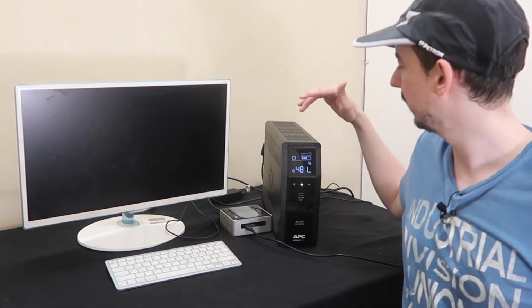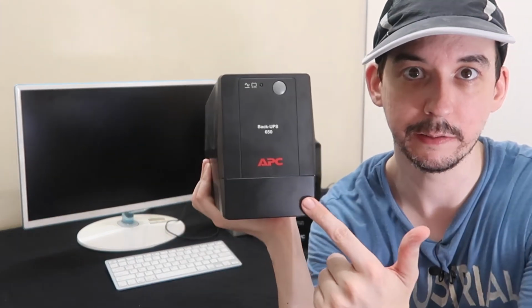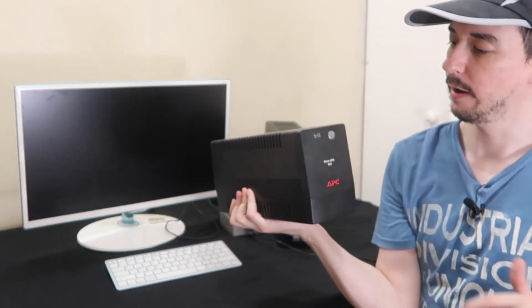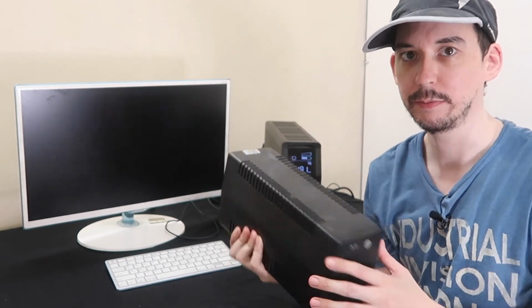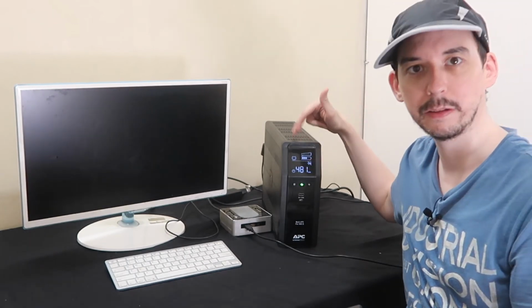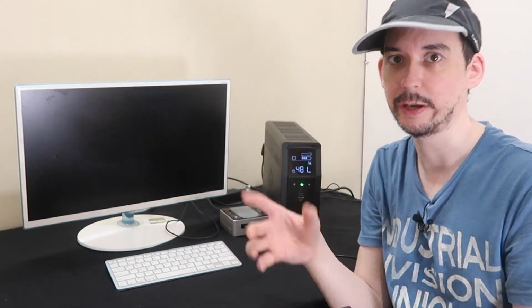So another difference between this UPS and this one here, this is also APC. I bought this myself. This is modified sine wave, and this bigger one is pure sine wave. So anything that's plugged into this is nearly the same as plugging it directly into your wall. Whereas what you plug into this gets a modified power. So instead of being a nice, smooth sine wave like that, it's a chopped sine wave, or almost like a pyramid where it's stepped to simulate a sine wave.